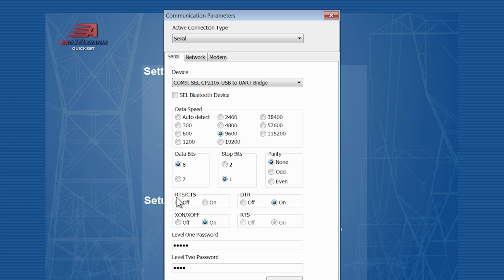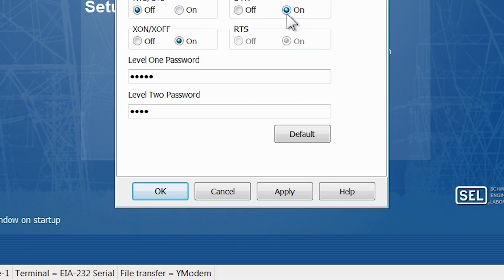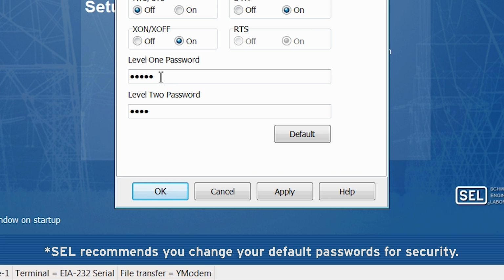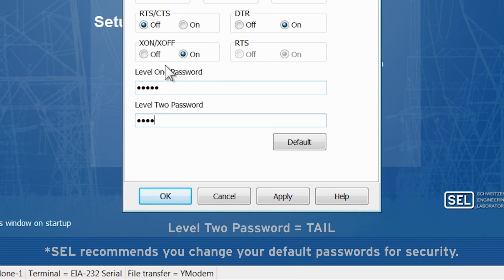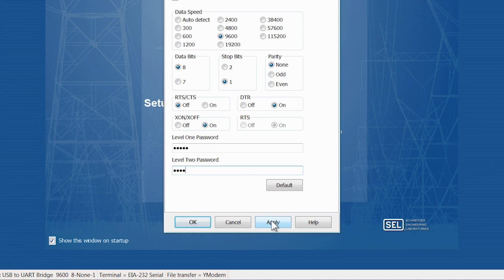The additional settings further down here, the data bits, stop bits, and parity, those typically you leave at the default. The level 1 password and the level 2 password are configurable. The default passwords, if you get an out-of-the-box 751 relay or another of our relay families, are: level 1 password OTTER, spelled O-T-T-E-R, all capitalized. The level 2 access level password is TAIL, T-A-I-L, all capitalized.